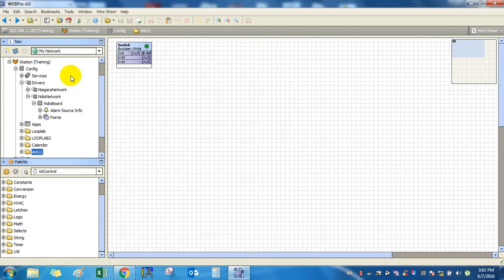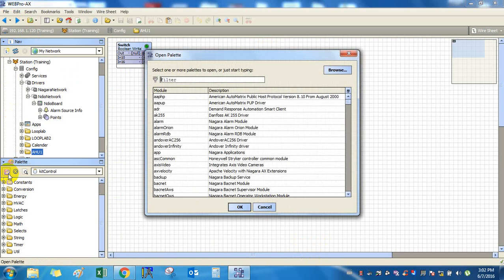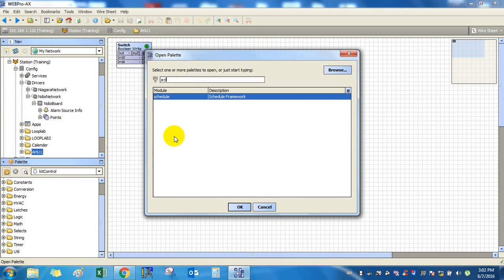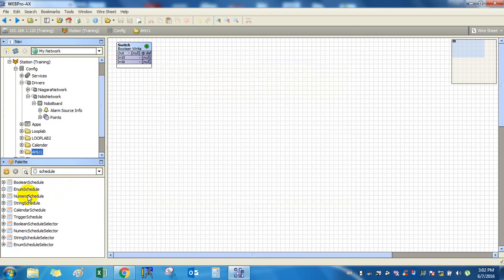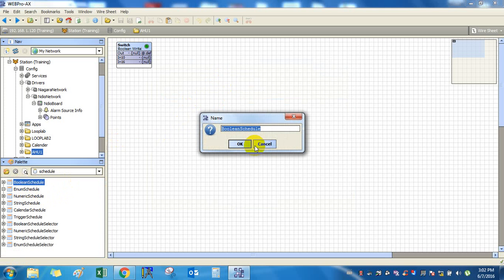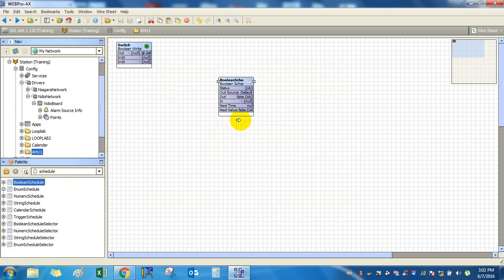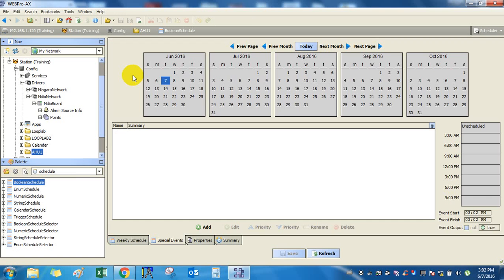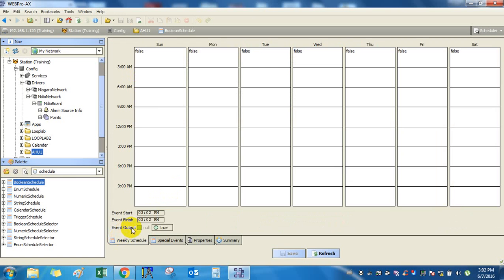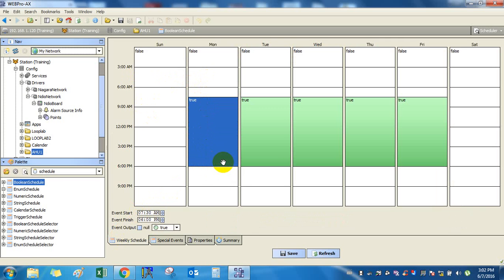Then we will add a schedule. For that we have to go to the schedule palette. Add a boolean schedule. Configure it from Monday to Friday, 8 to 6. Save. In properties, change the facets to occupied, unoccupied.